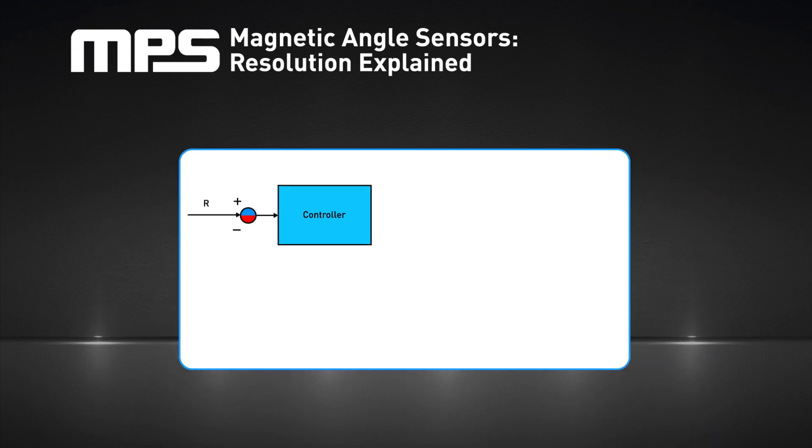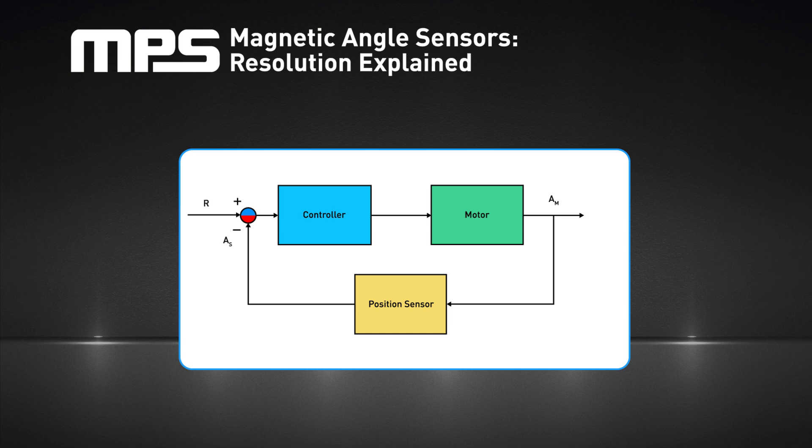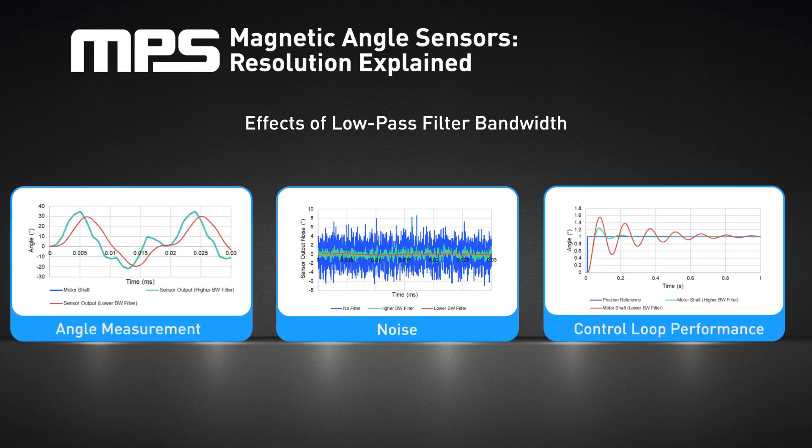A bandwidth that is too low for an application can have dramatic effects. If the sensor is used inside a control loop, the system may be unstable, and the motor may exhibit oscillations, noise, and or loss of efficiency. In this figure, R is the position reference, AM is the motor shaft angle, and AS is the sensor output. A common design rule is to have the filter bandwidth be at least 10 times larger than the bandwidth of the control system or control loop. These figures show the effects of a low-pass filter bandwidth on the angle measurement, the noise, and the control loop performance, respectively.